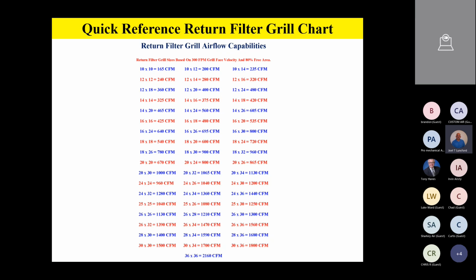So on the air side, and sometimes, guys, I get a little bit preachy on this because I'm really adamant about proper airflow. Anytime you reduce airflow for whatever reason, whether it's undersized ductwork, pleated filters, a dirty evaporator coil, any of that stuff, it reduces the capacity of the unit. And not only does it reduce capacity, but it also decreases the ability of that unit to remove humidity. Now, if your airflow falls anywhere between about 350, 375 to 400, I'm not going to sweat it.